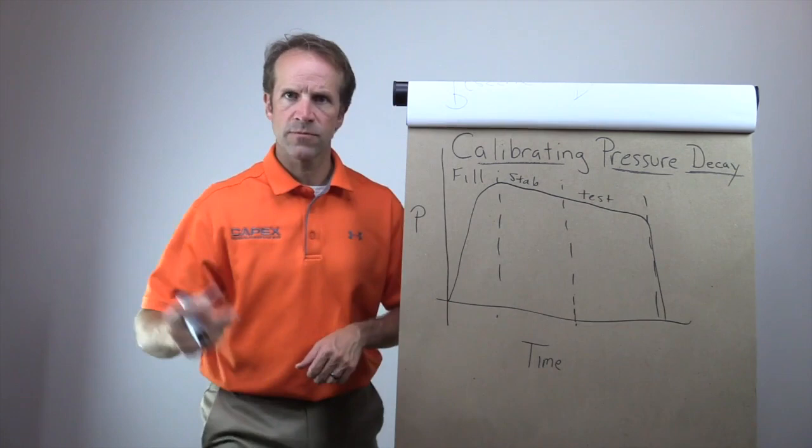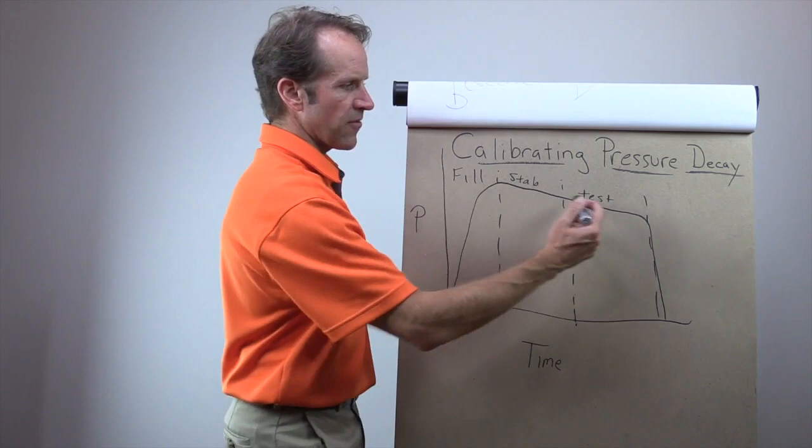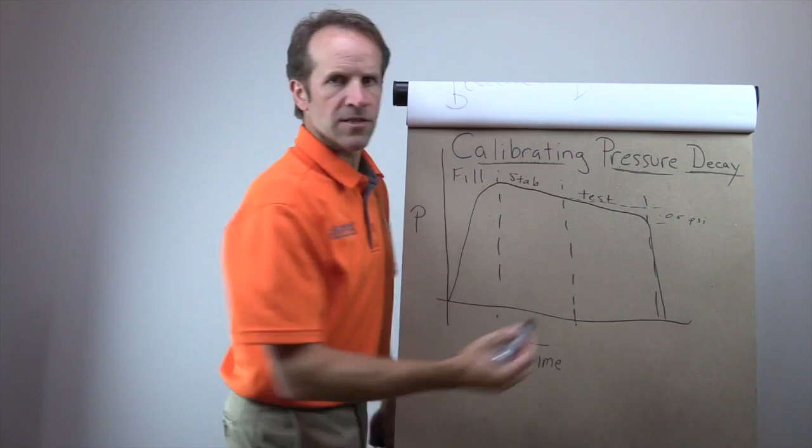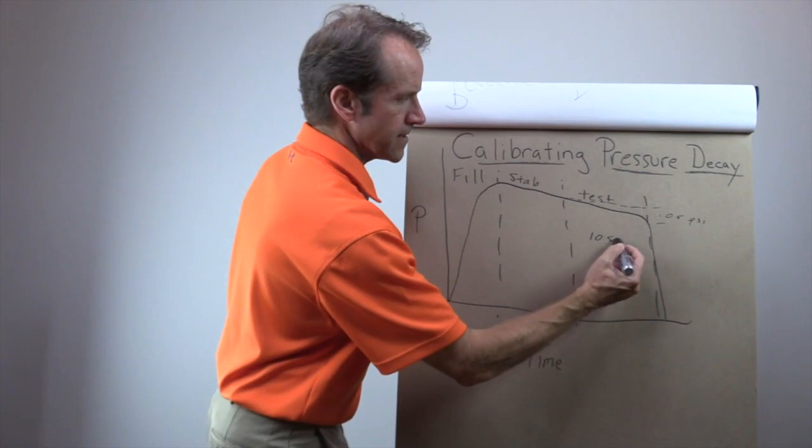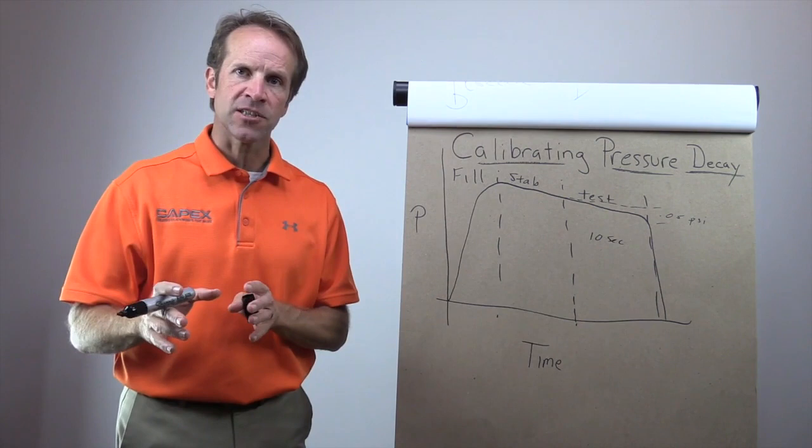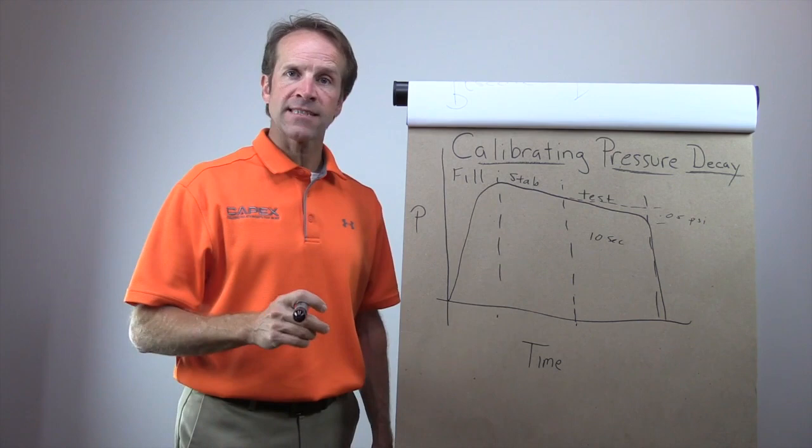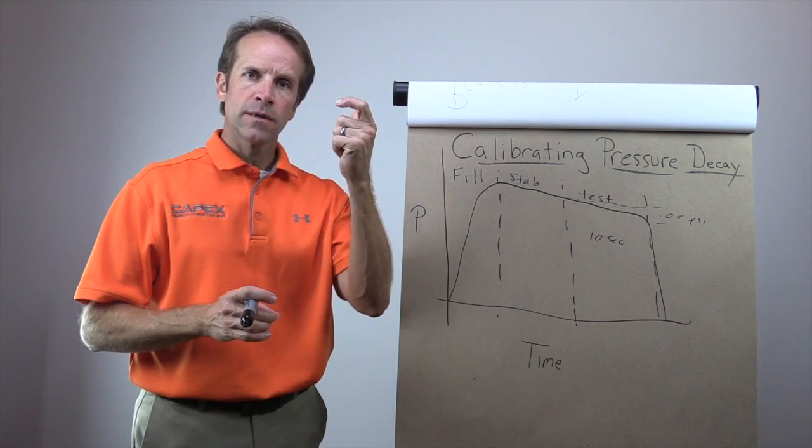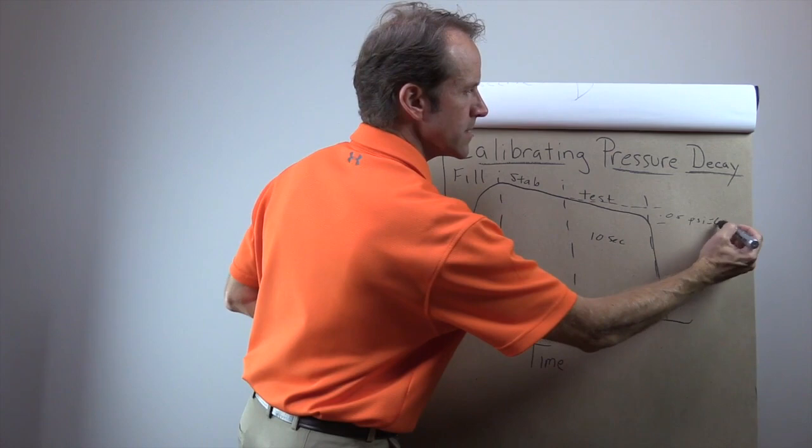Right here at the end, obviously, we're dumping all the pressure out of the part. So we run our first test, and it's going to measure the amount of pressure loss from this point to here. So let's say it's 0.05 psi. 0.05 psi pressure loss during this, let's say it was 10 seconds. So over 10 seconds, we lost 0.05 psi from our known good part. So to the instrument, 0.05 psi now becomes 0 SCCM. So every part that you run after this calibration, if it leaks 0.05 psi, it will display 0 standard cubic centimeters per minute. So 0 SCCM equals 0 SCCM.